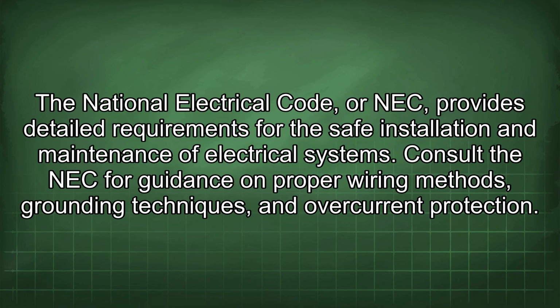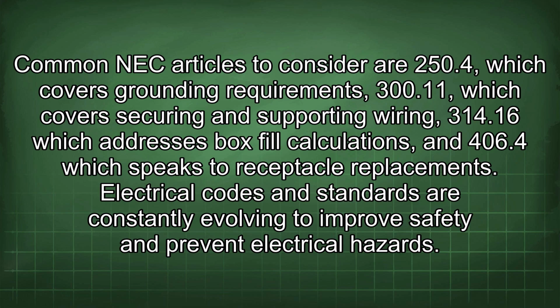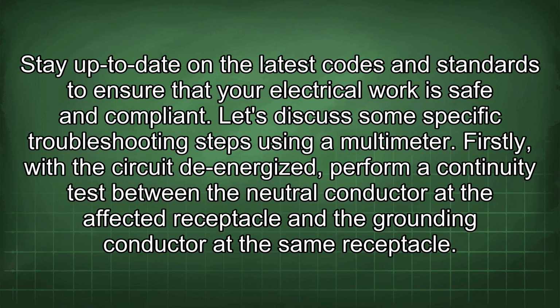The National Electrical Code, or NEC, provides detailed requirements for the safe installation and maintenance of electrical systems. Consult the NEC for guidance on proper wiring methods, grounding techniques, and overcurrent protection. Common NEC articles to consider are 250.4, which covers grounding requirements, 300.11, which covers securing and supporting wiring, 314.16, which addresses box fill calculations, and 406.4, which speaks to receptacle replacements. Electrical codes and standards are constantly evolving to improve safety and prevent electrical hazards. Stay up to date on the latest codes and standards to ensure that your electrical work is safe and compliant.